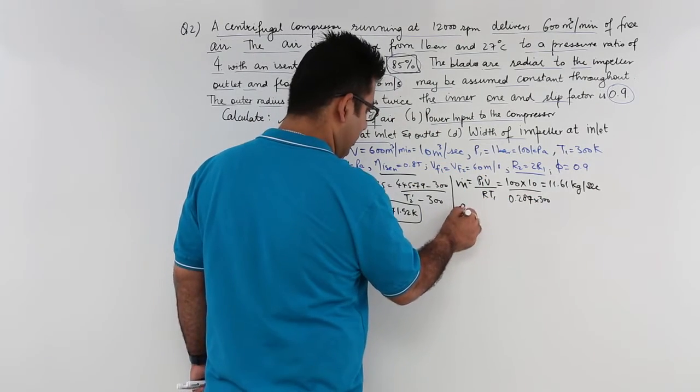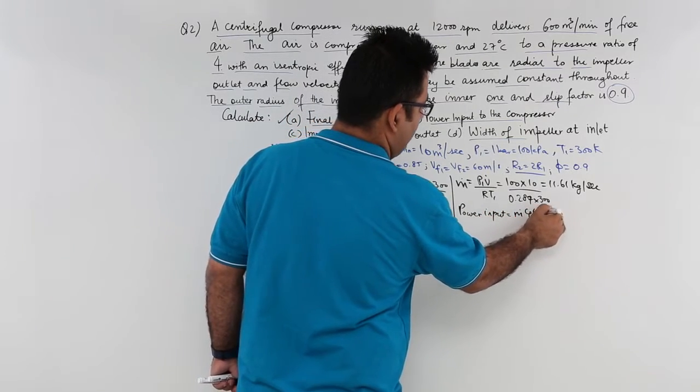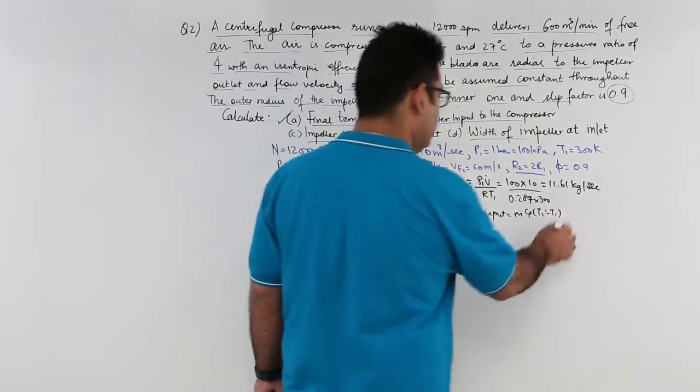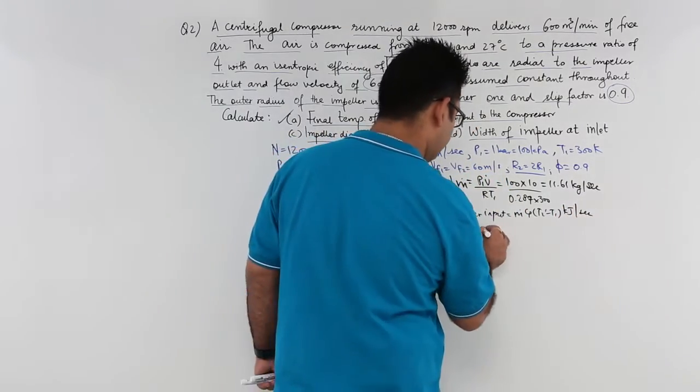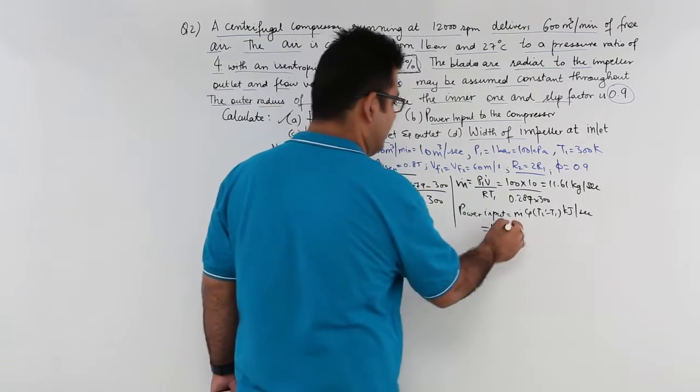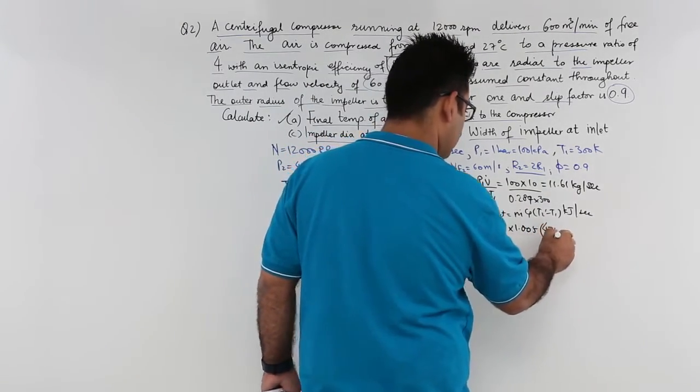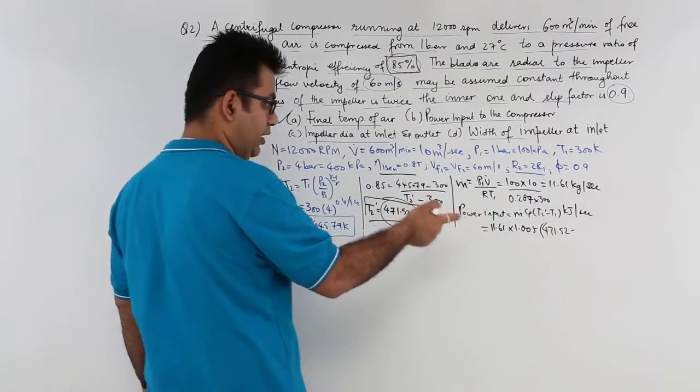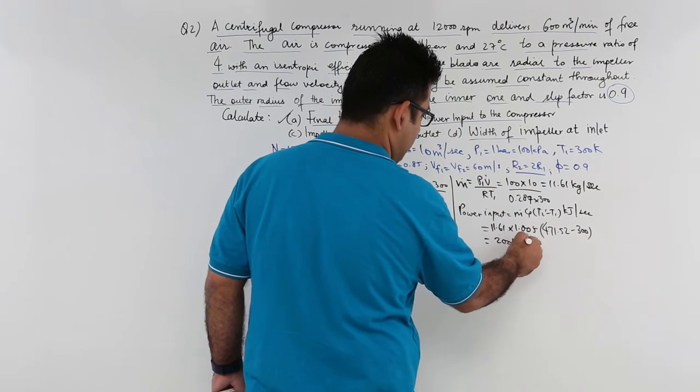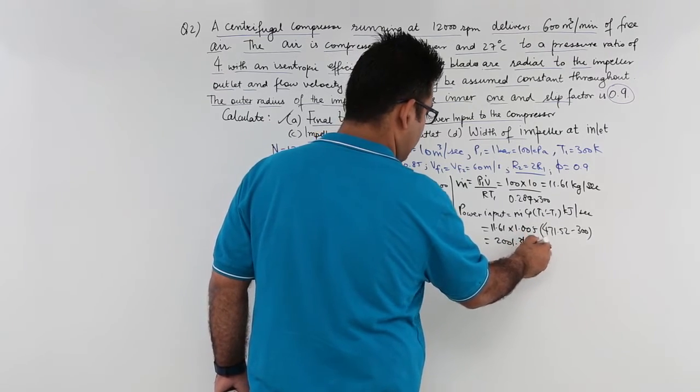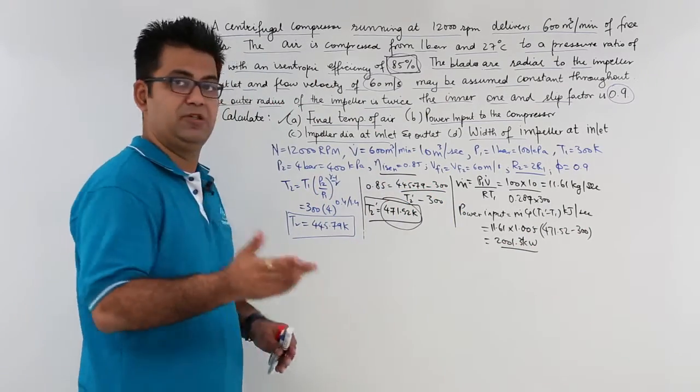Now to find out power input it is a simple thing which is M dot Cp T2 dash minus T1. So M dot is 11.61, CP for air is 1.005, T2 dash is 471.52 minus T1 is 300. This will give you a power input of around 2001.3 kilowatts. So this much amount of power has to be given in order to get this kind of performance from your centrifugal compressor. Now the second part of the question is also done.